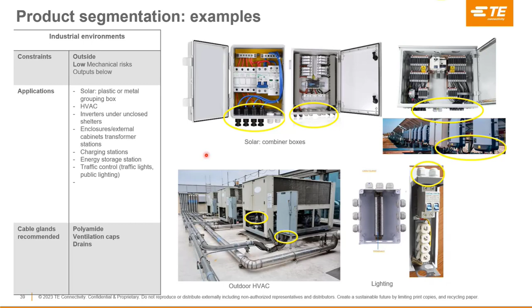So the ventilation is actually creating this circulation of pressure between the two, and then the drain, if there's humidity because of temperature differences, helps to drain and evacuate the water at the bottom of the panel. These are all things you can use when you're outside, because you have higher temperature differences.